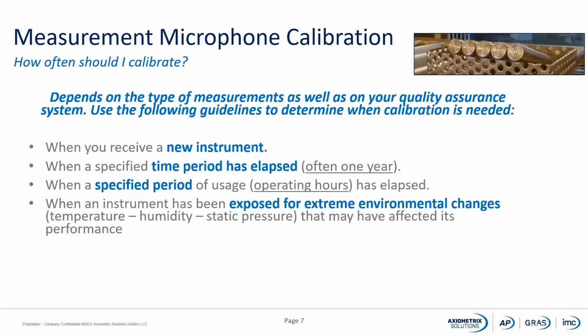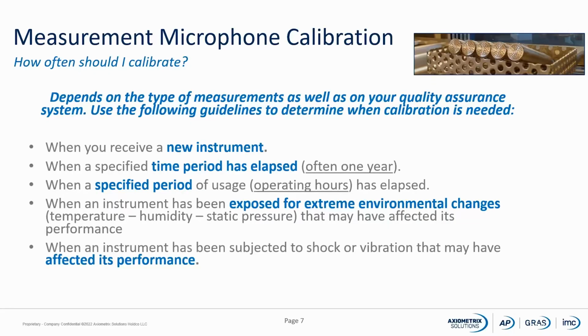When an instrument has been exposed to extreme environmental changes, such as temperature, humidity, static pressure, that might have affected its performance, then it's a good idea to perform a calibration. When an instrument has been subjected to shock or vibration, and this might have affected its performance, then it's also a good idea to perform a calibration.